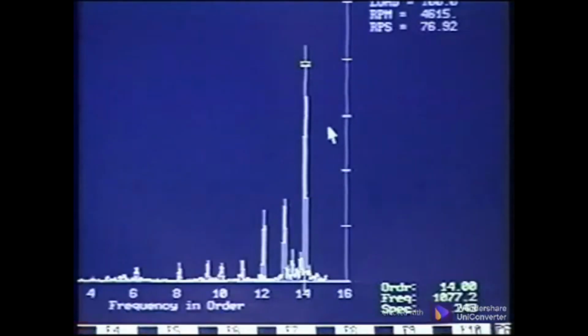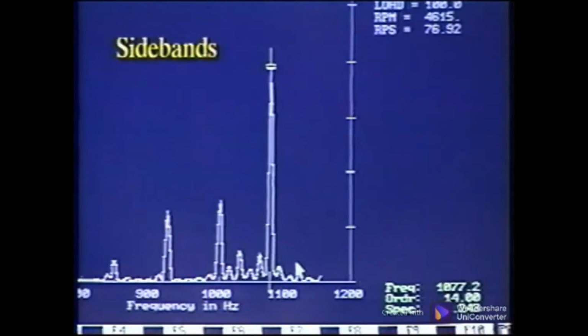One characteristic of gear mesh frequencies indicating a problem is that the gear mesh frequency is modulated by another frequency. This modulation shows up as sidebands around the gear mesh frequency. Sidebands are peaks that are evenly spaced to either side of a frequency. There may be more than one sideband on each side. One side may have more sidebands than the other.